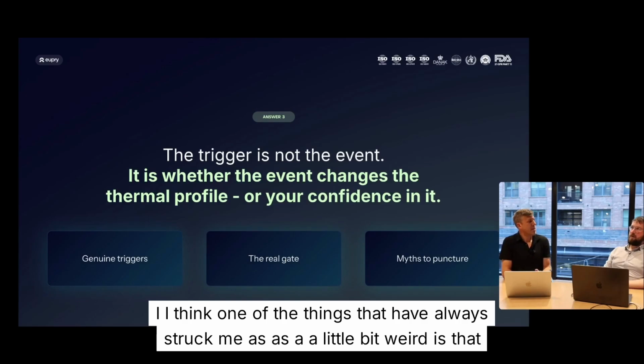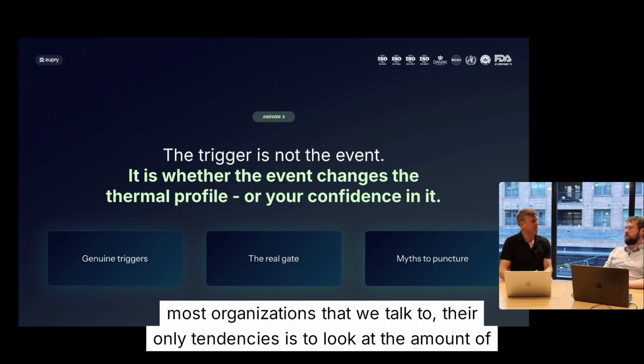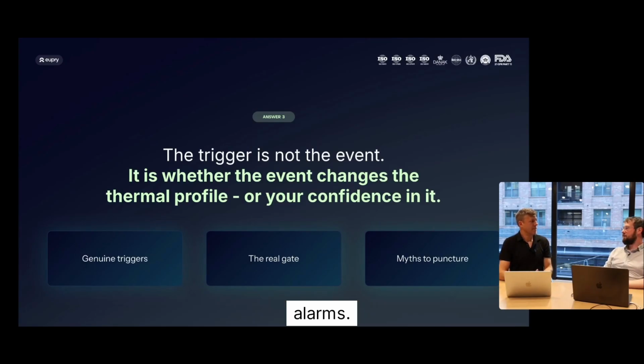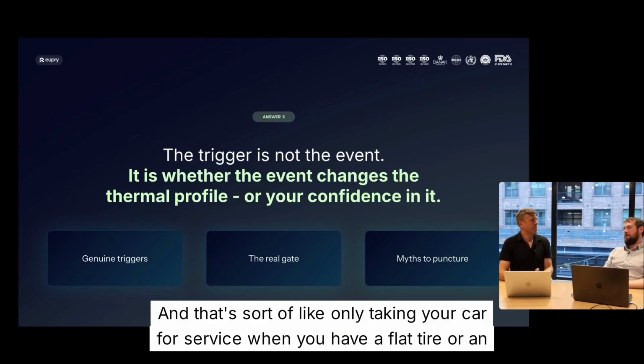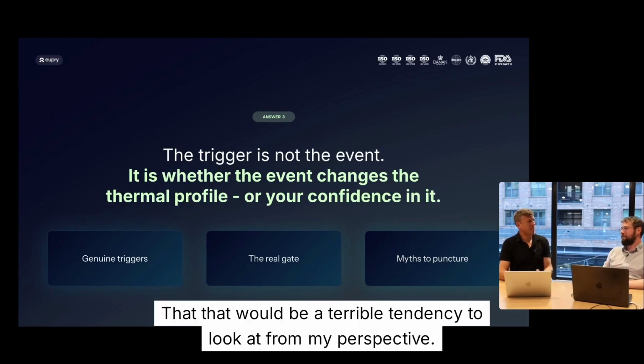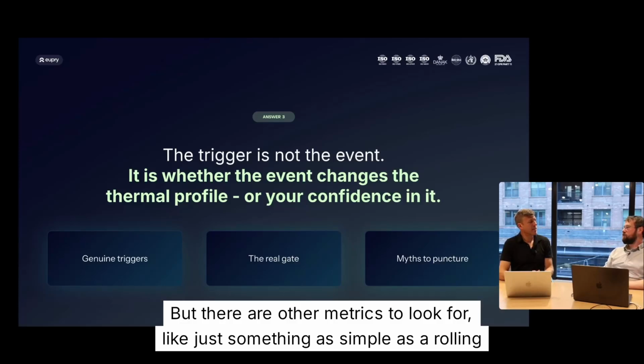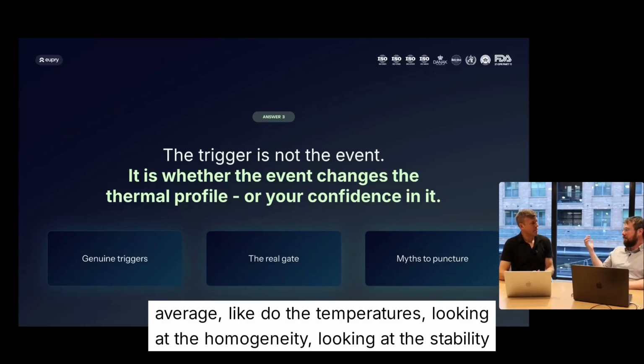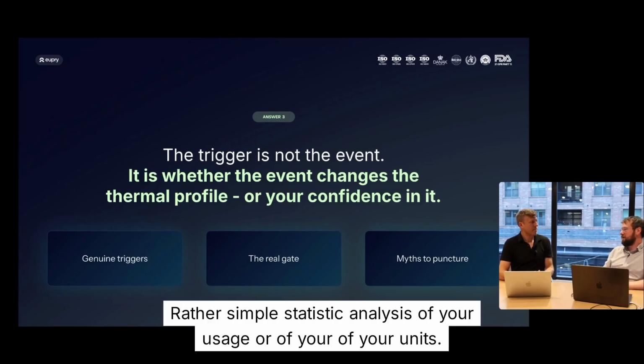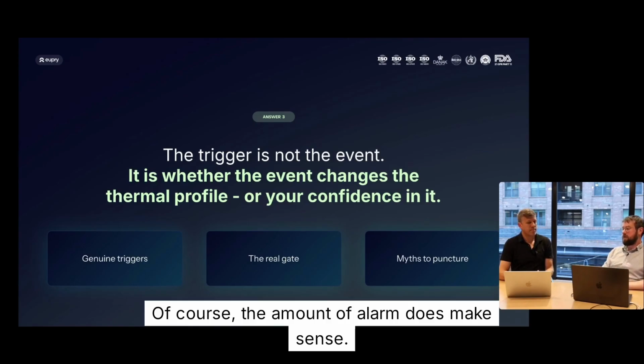I think one of the things that has always struck me as a little bit weird is that most organizations we talk to only look at the amount of alarms as their tendency. That's sort of like only taking your car for service when you have a flat tire or an engine problem. Well, it's too late at that point. That would be a terrible tendency to look at, from my perspective. But there are other metrics to look at, like something as simple as a rolling average, the homogeneity and stability of temperatures, rather simple statistical analysis of your units. Of course, the amount of alarms does make sense.